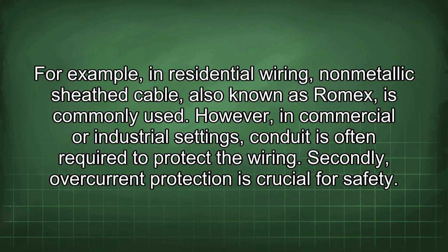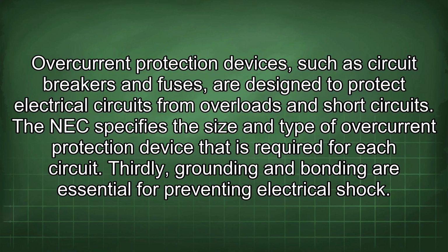For example, in residential wiring, non-metallic sheath cable, also known as Romex, is commonly used. However, in commercial or industrial settings, conduit is often required to protect the wiring. Secondly, overcurrent protection is crucial for safety. Overcurrent protection devices, such as circuit breakers and fuses, are designed to protect electrical circuits from overloads and short circuits. The NEC specifies the size and type of overcurrent protection device that is required for each circuit.